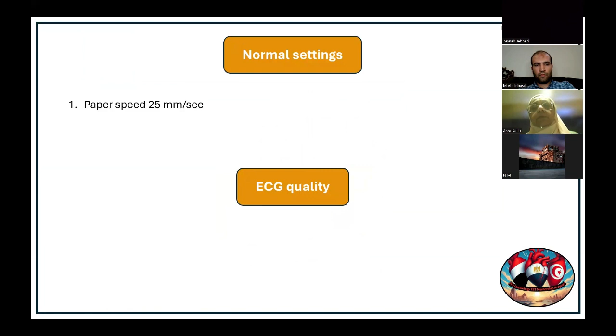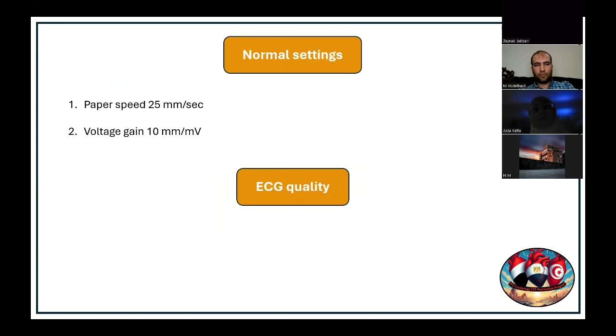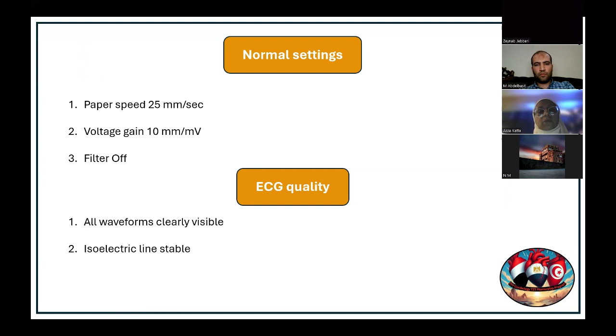For the ECG, the paper speed should be 25 millimeters per second. The voltage gain should be 10 millimeters per millivolt, and the filter should almost always be off. The ECG quality is judged by the waveforms. All the waveforms, the deflections that we will be seeing on the ECG paper, should be clear and visible, and especially the isoelectric line should be stable. So these are the normal settings and the good quality ECG that we should look for before starting to interpret the ECG.